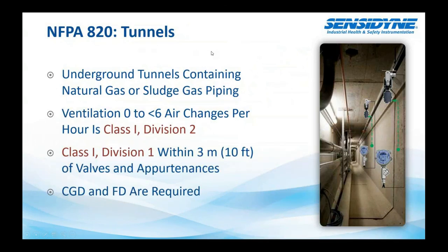Don't see these a lot in Florida, but you run across them here and there. You can also come into some tunnels. Tunnels should always be monitored, underground tunnels containing natural gas or sludge gas piping. Any of these pipings and a lot of stuff can leak. If you're having people go in here to do your maintenance and service in these areas, these are definitely a place where you'll want to obviously monitor for explosives and hazardous or toxic gases.